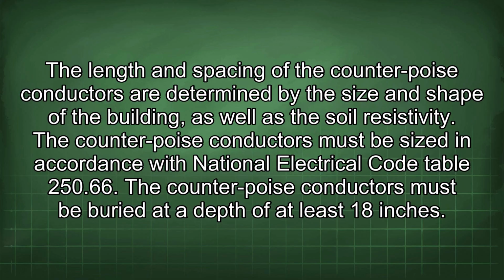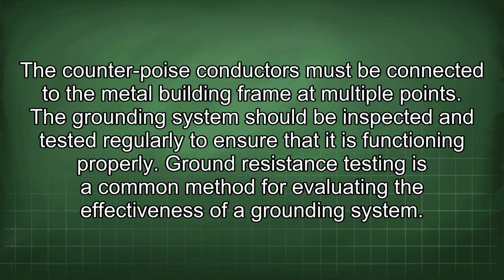The counterpoise conductors must be sized in accordance with National Electrical Code Table 250.66. The counterpoise conductors must be buried at a depth of at least 18 inches. The counterpoise conductors must be connected to the metal building frame at multiple points. The grounding system should be inspected and tested regularly to ensure that it is functioning properly. Ground resistance testing is a common method for evaluating the effectiveness of a grounding system.